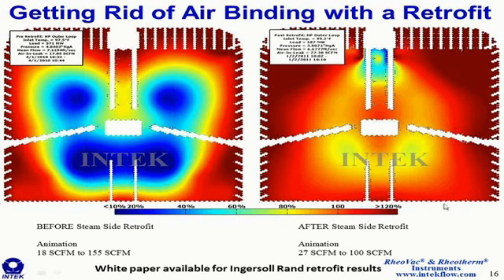So you can see side by side the impact that we have made on the air binding by installing a condenser retrofit. You can see the deep blue regions where there's essentially no heat transfer occurring in the bundle, on the pre-retrofit side, the left side, and then after the retrofit in the same bundle, you can see those blue regions are completely eliminated. And so I have an animation prepared for you on these bundles as well. The left side, we're going to animate this bundle from 18 SCFM up to 155 SCFM. On the right side, we'll show you the after retrofit performance when the air in leakage is increased from 27 to 100 SCFM.